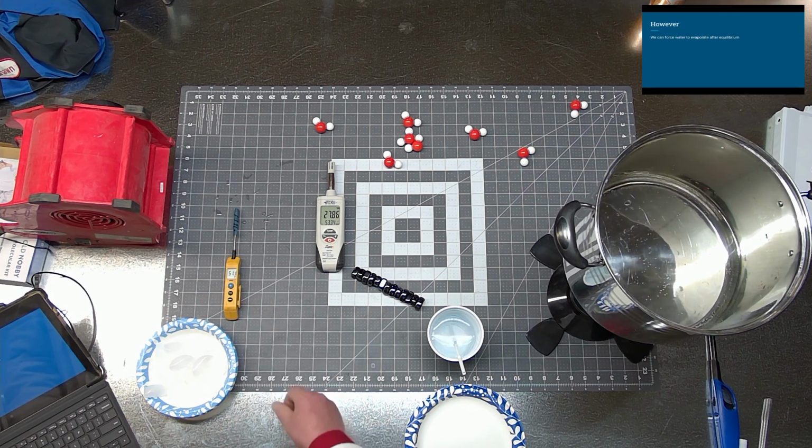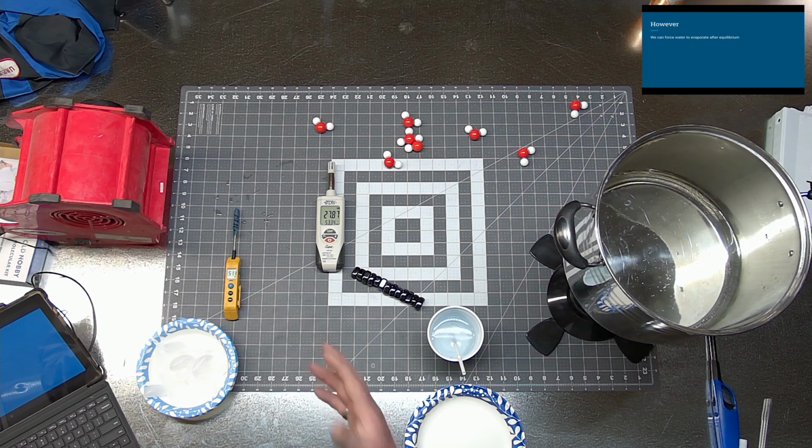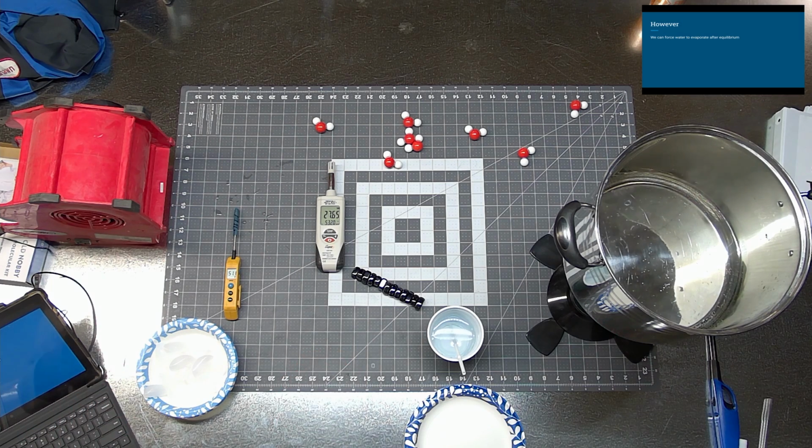51 degrees. So we had like a 24 degree temperature delta T. And that's pretty good, because that's what you can expect out of a cooler with fully saturated pads when there's that big of a differential. So evaporative coolers work pretty well until that point where the wet bulb starts to come up to the dry bulb temperature. There's just nothing you can do at that point.